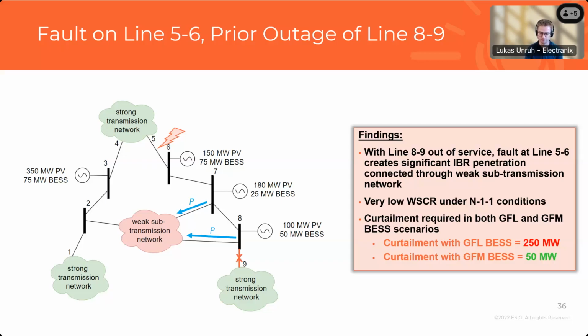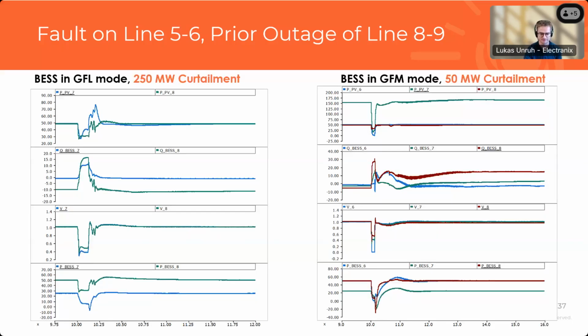So with grid following, we had to reduce the generation by 250 megawatts, which didn't really leave a whole lot left here. Whereas with grid forming, we only had to reduce by 50 megawatts. Next slide, Ryan. And here's just a plot showing the results of the system with the different curtailment levels.